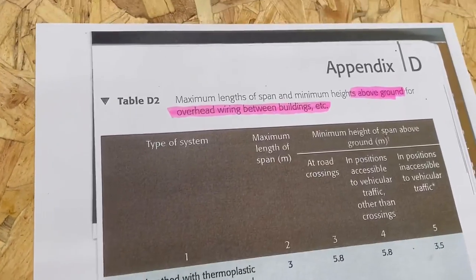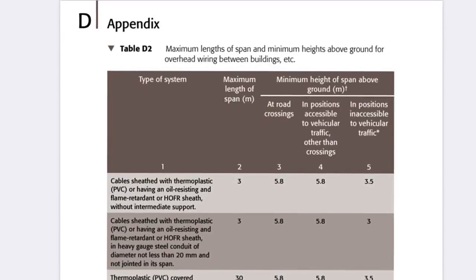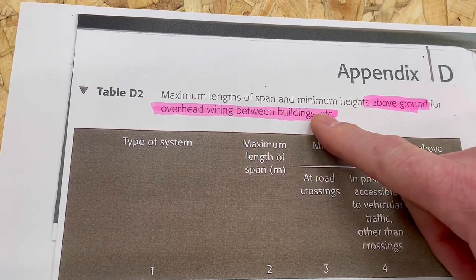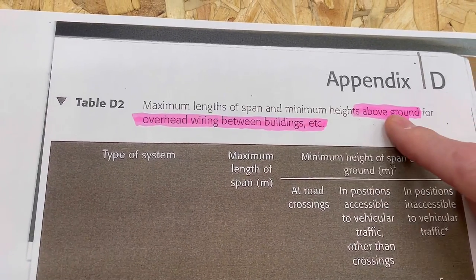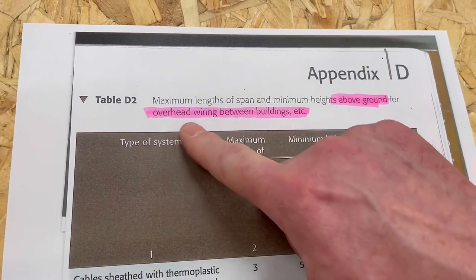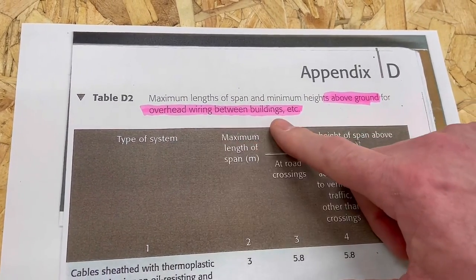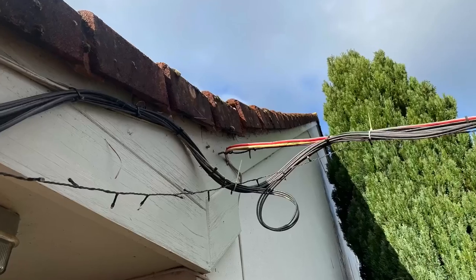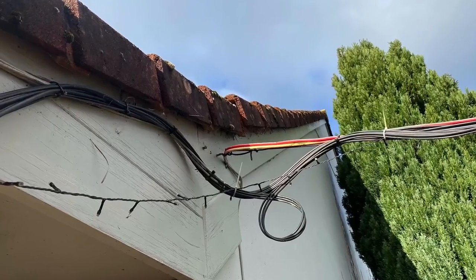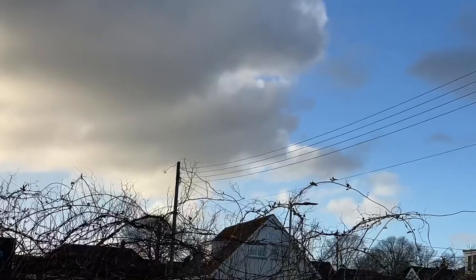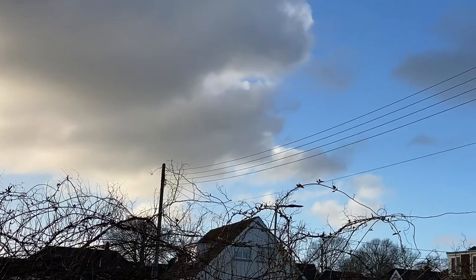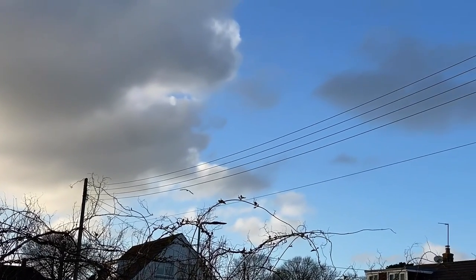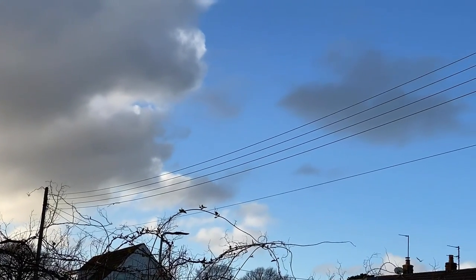I've brought in a blown-up version and also made some highlights on it. The table covers the maximum length of span and minimum height above ground for overhead wiring between buildings. We'll be talking first about the catenary wire, but there are some other types that you'll see walking around your town or village that also have cables above ground.